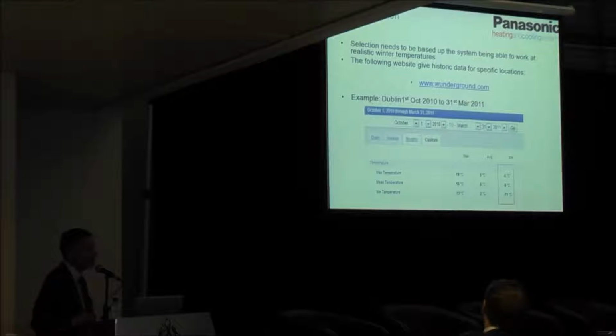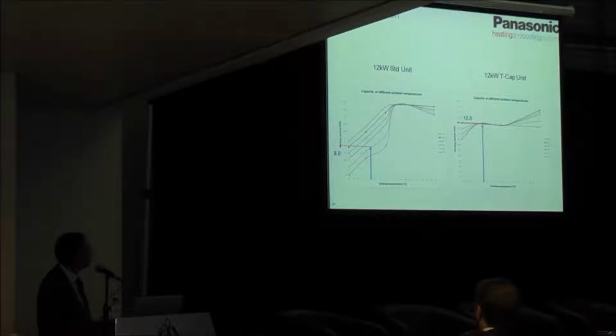So what do we design to? Do we design to -11? Probably not, because we're probably going to be oversizing our units. But certainly we should be looking at maybe around -5. So looking at a unit then to heat that 11 kilowatts heating capacity. A standard 12 kilowatt unit, which you would think would perhaps be able to do a 11 kilowatt load, but a standard unit with water at 50 degrees C, we're only getting 9 kilowatts.